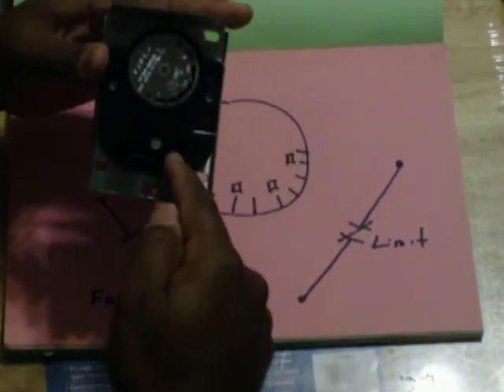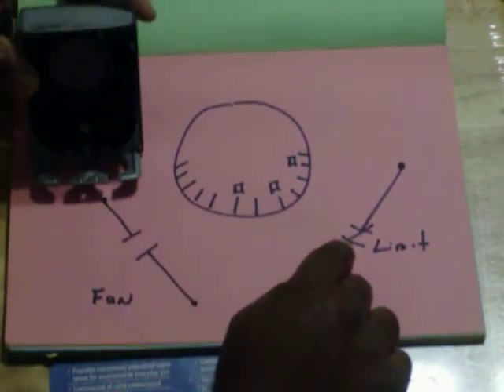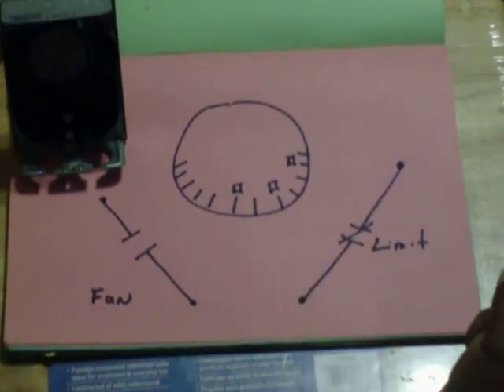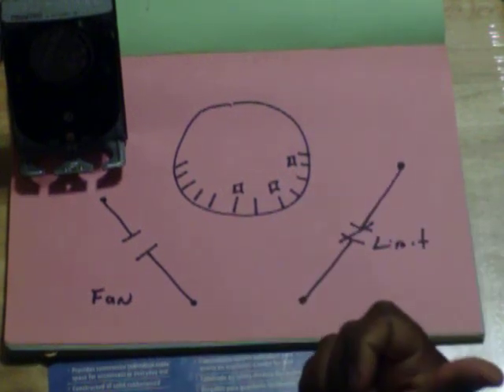Looking at this, here is that dial I drew. And one set of switches is between here and here. One set is between here and here. Your normally closed is your limit. So you would come out of your transformer, go straight to your limit, leave the limit, then you go to your thermostat.